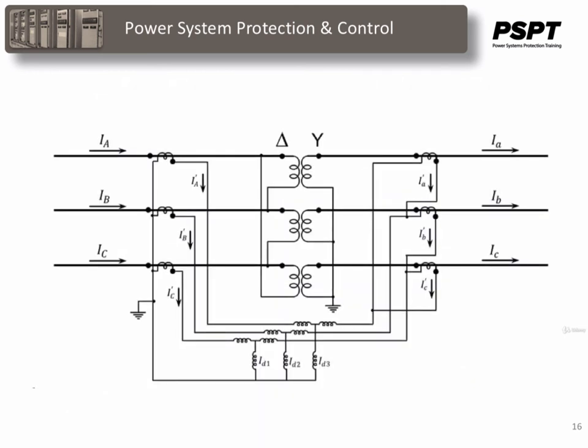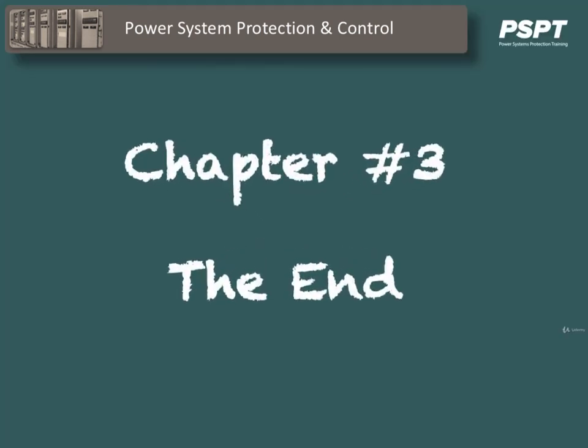This is another example, this time on a protection circuit for a transformer differential protection circuit. You can see that the markings for the PTs and the CTs are designated with circles, and in the case of the actual power transformer itself, the polarity markings are indicated in the same manner. This is the end of Chapter 3.